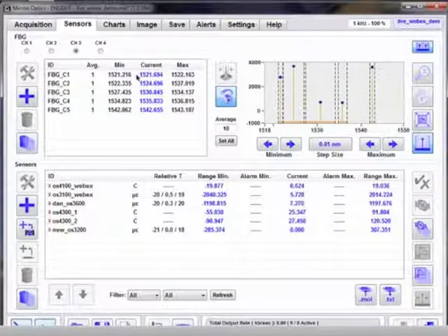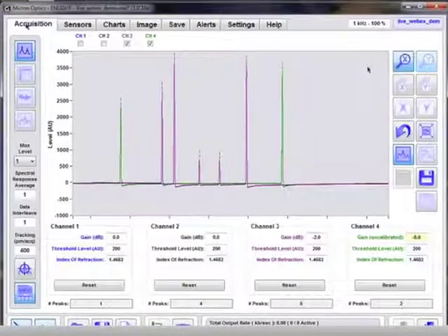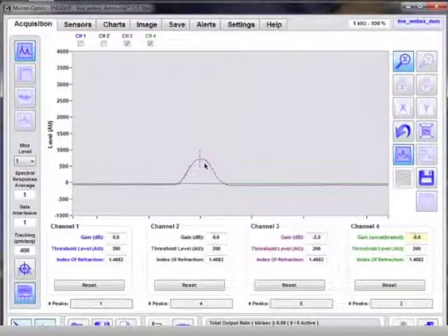One thing I would like to point out there on averaging of the full spectrum is, again, as we mentioned earlier, the full spectrum has 32,000 points, depending on which interrogator. If you do set that averaging to a very large number, say 500 or 1,000, your time response becomes very, very slow, and two, you are consuming a considerable amount of memory. And I've seen times where that was set high enough that it was able to use up all the available RAM on the system and cause issues, to say the least.